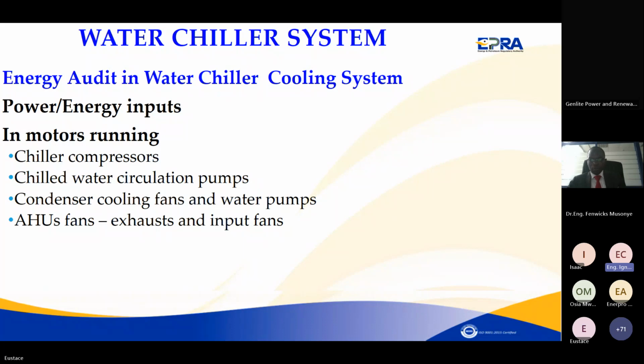In this case, the starting point, as you clearly put it, is establishing the cooling loads first. So whichever system you'll be auditing, establishing the load requirement helps you understand whether the system is oversized or undersized, and then you can focus on the optimal requirements, optimal temperature requirements, and whether the system is working close to optimal.